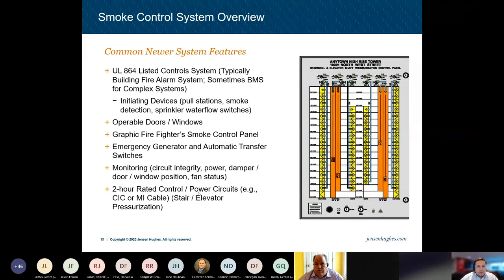So some common newer system features that you'll see in a smoke control system, you'll have a UL 864 UUKL listed control system. Like I said, it's typically the building fire alarm system, but sometimes it can be the BMS for complex systems where you may be having non-dedicated equipment doing dual duty. As part of that system, you're going to have initiating devices, so pull station, smoke detection, sprinkler water flow switches, what's automatically initiating that system to operate. As I mentioned previously, you'll have operable doors and windows that are providing makeup air. So those are automatically opening in a smoke event or a fire event to provide makeup air to the required exhaust system.